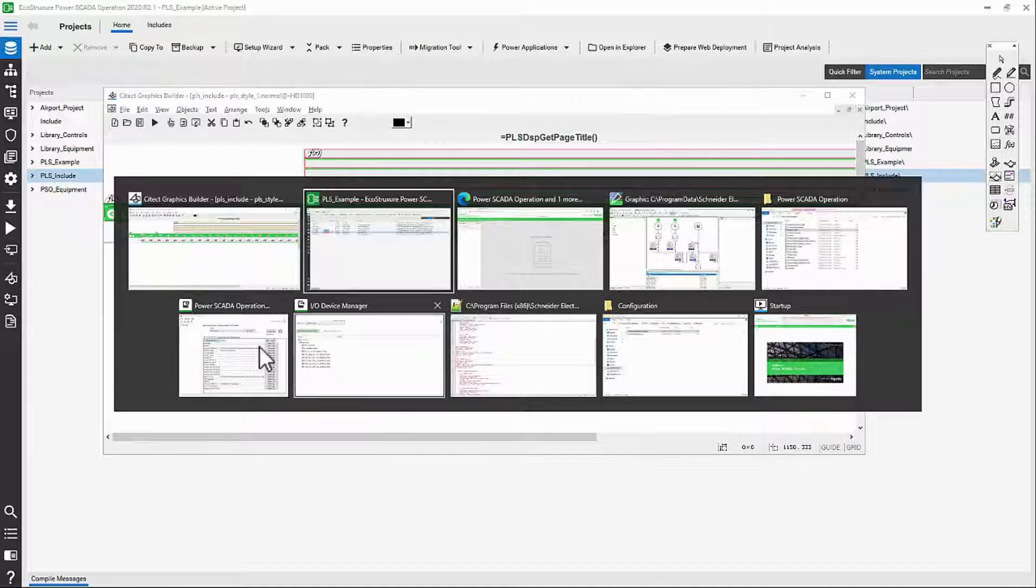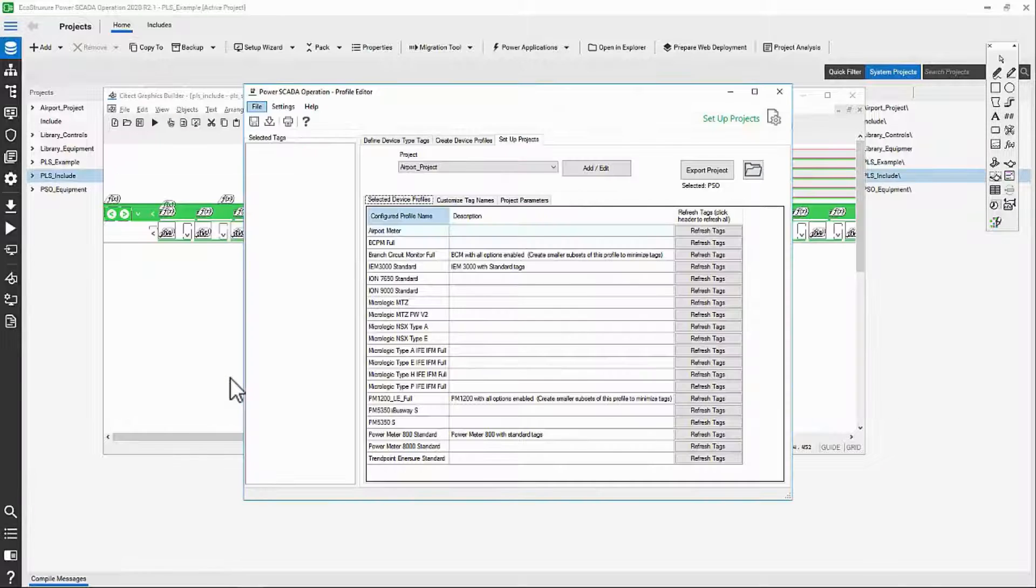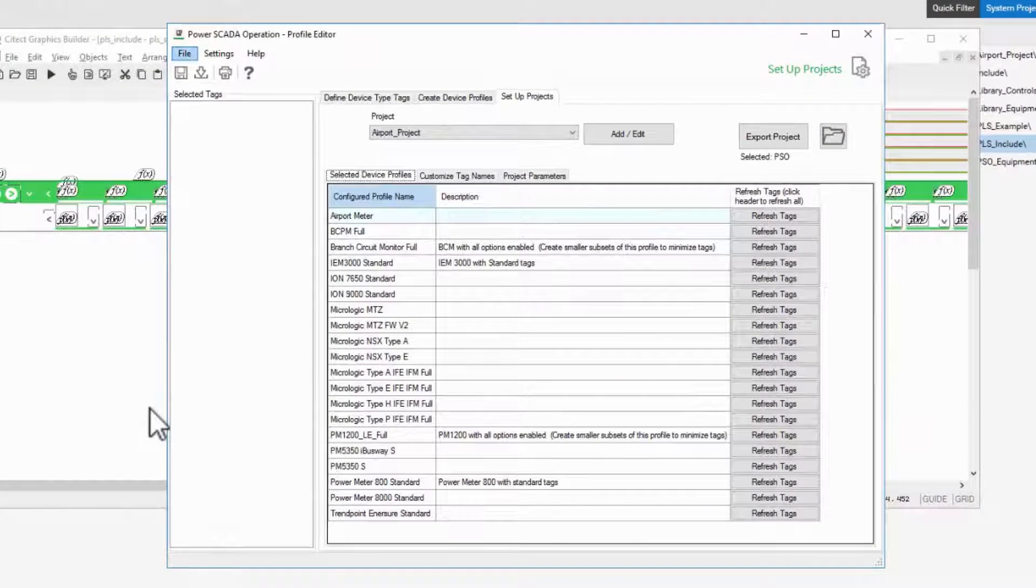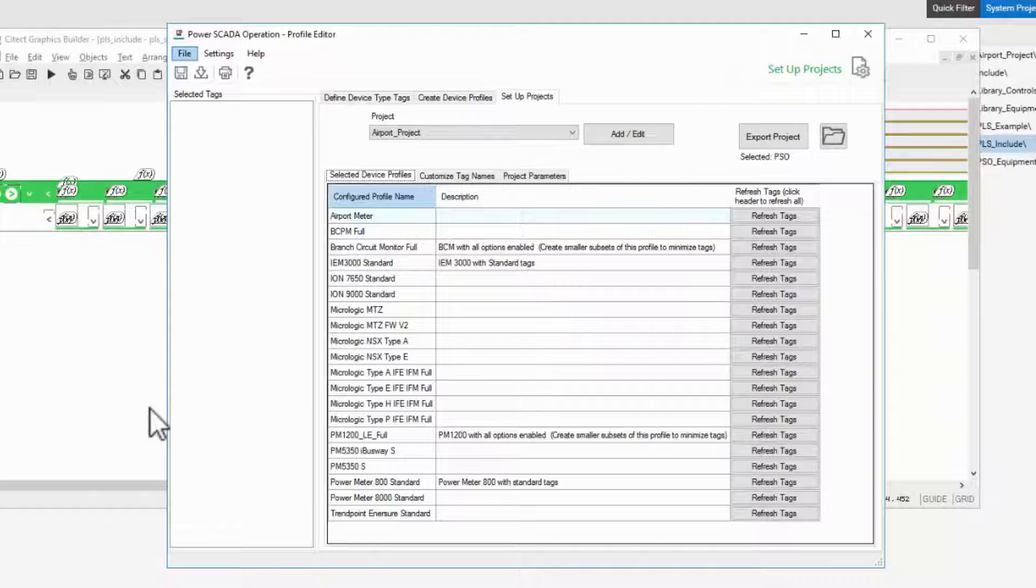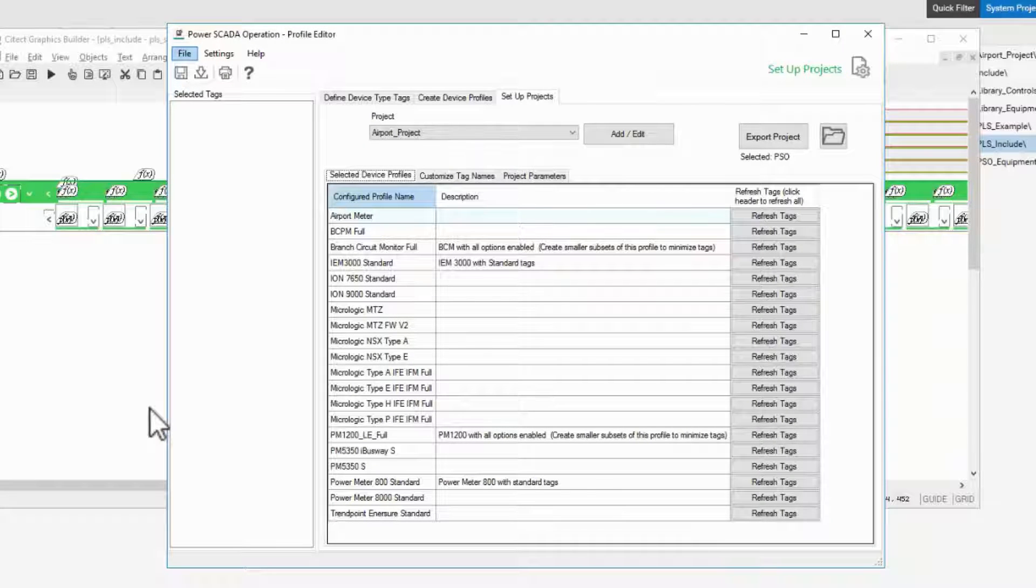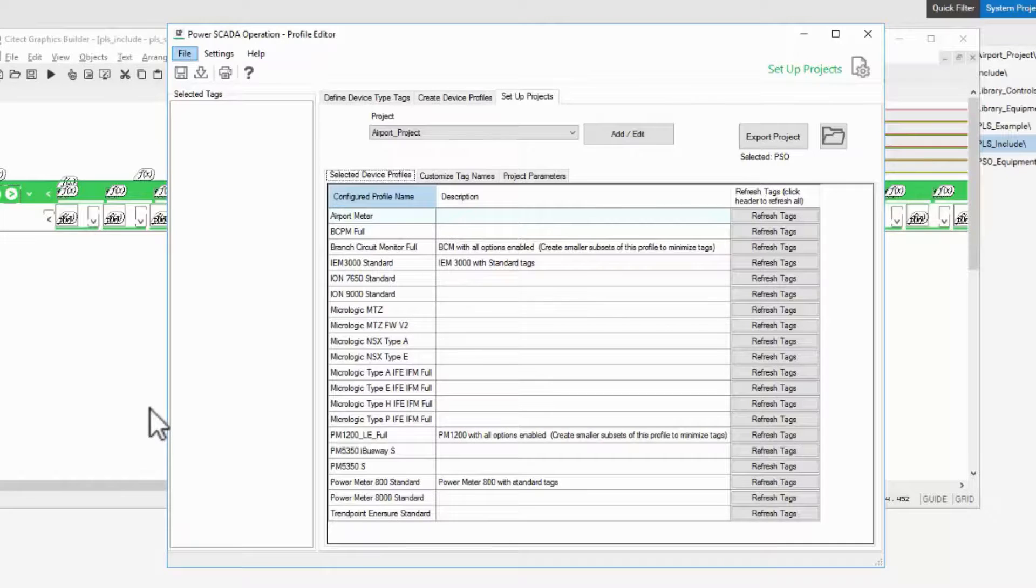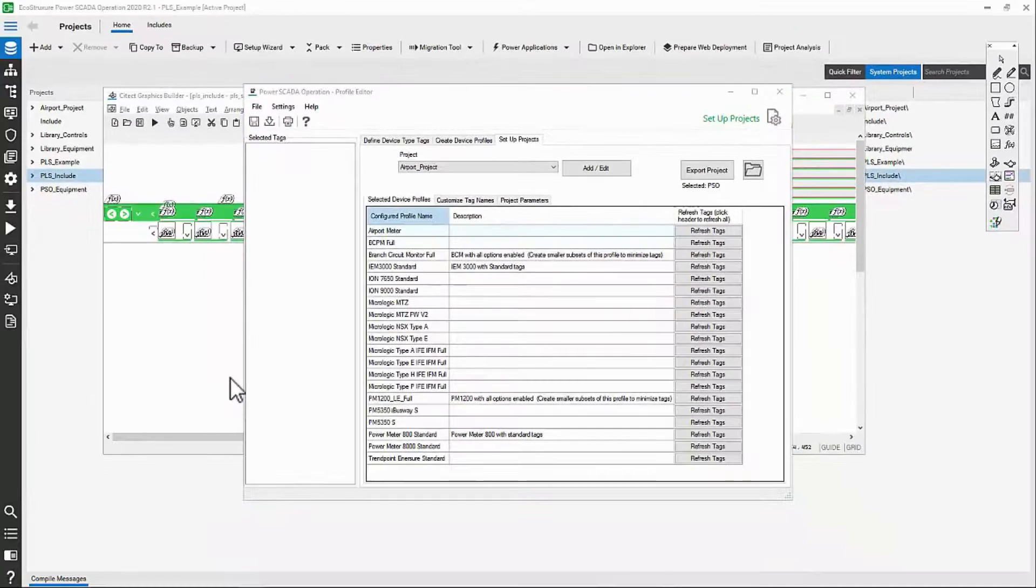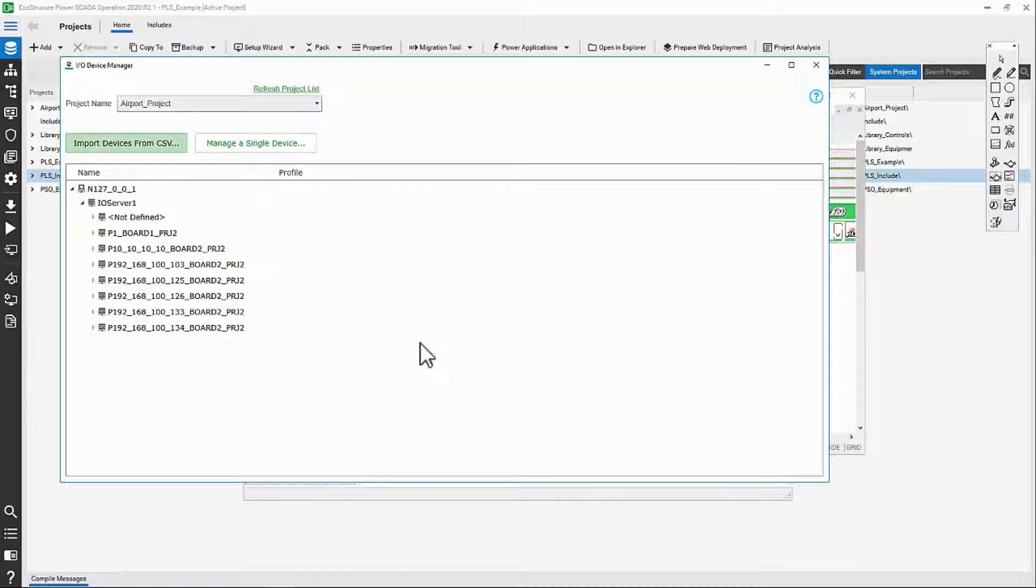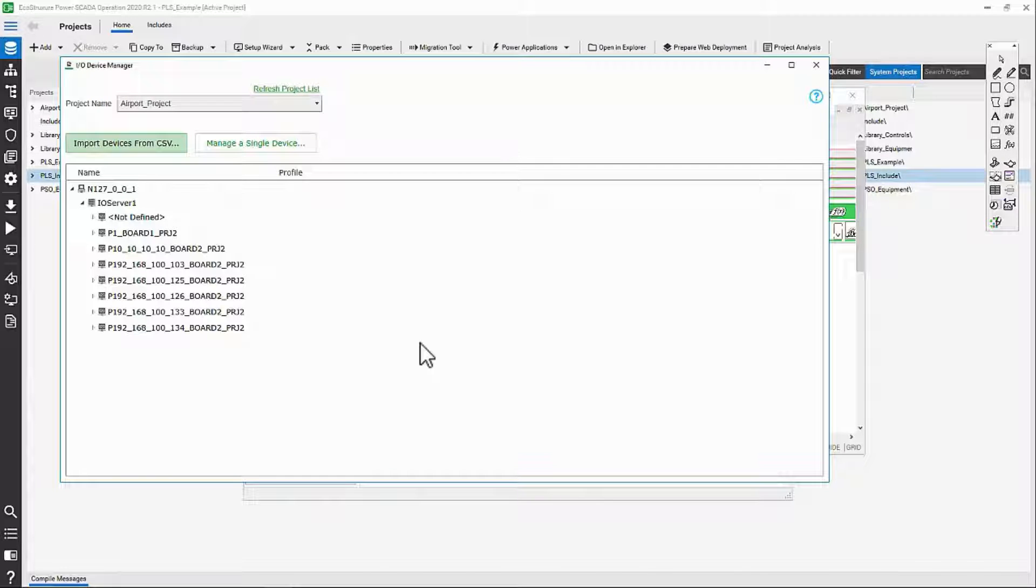The largest of these is Profile Editor, which allows us to build standard templates of what the different types of equipment look like and how their tags are addressed. These profiles are used by the IO Device Manager to automatically populate the databases with devices, variable tags, alarm tags, and parameters. Think of this as the replacement for the Express Wizard.